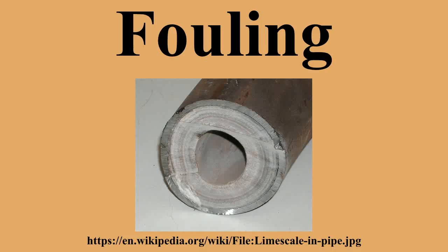Asymptotic fouling. Here, the fouling rate decreases with time, until it finally reaches zero. At this point, the deposit thickness remains constant with time. This is often the case for relatively soft to poorly adherent deposits in areas of fast flow. The asymptote is usually interpreted as the deposit loading at which the deposition rate equals the deposit removal rate.